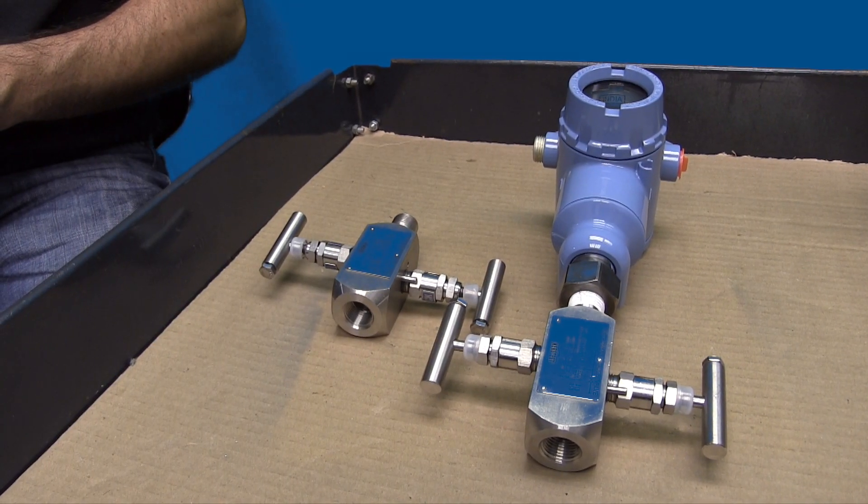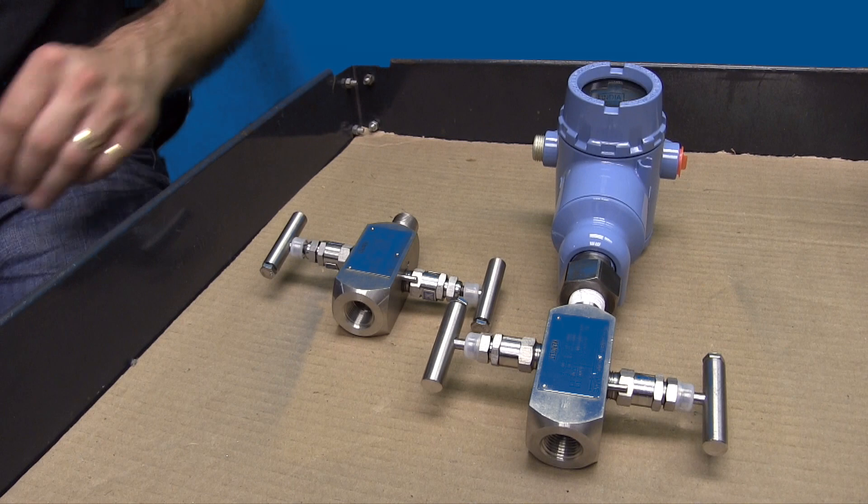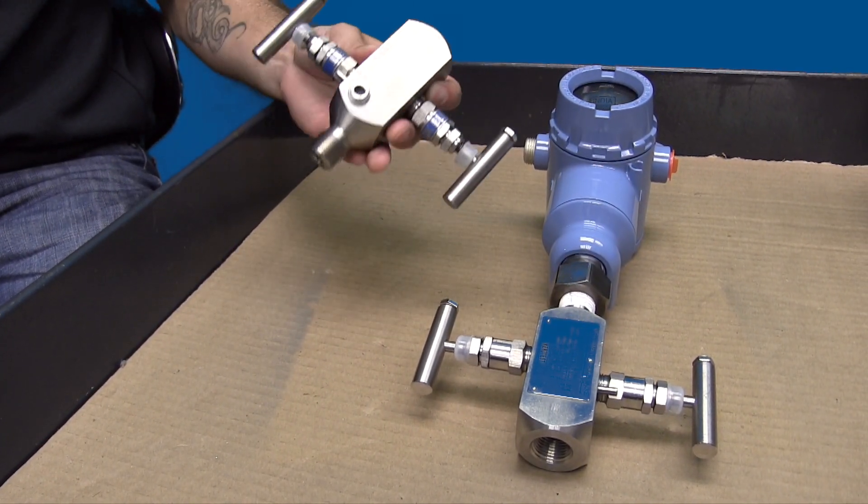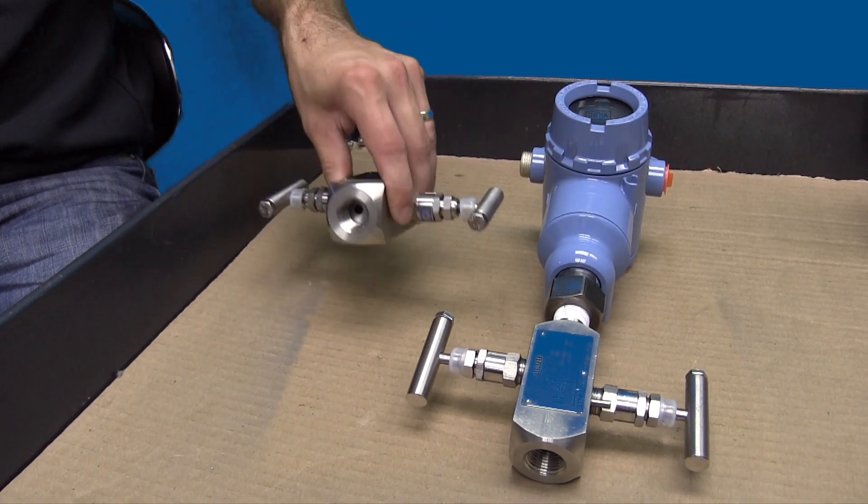In-line manifolds are used on direct connect style sensors. These are usually two-valve, half-inch NPT combinations involving female and male connections. They are also called block and bleed manifolds.